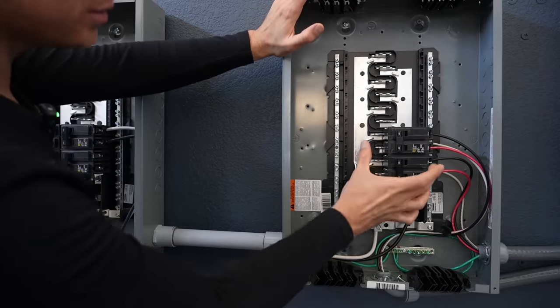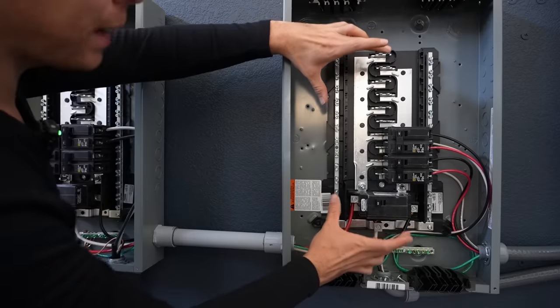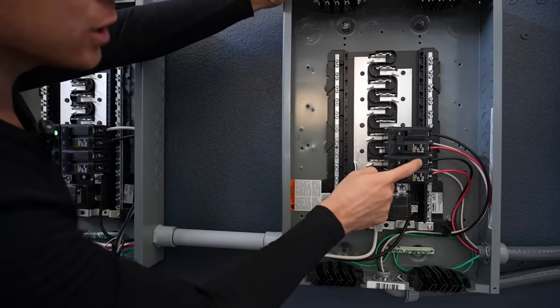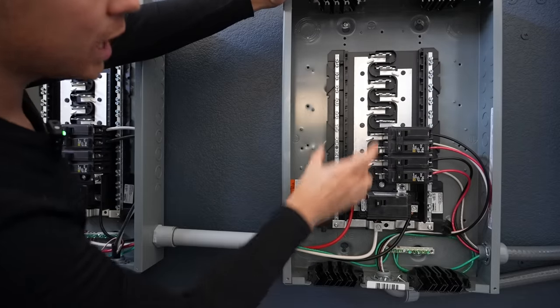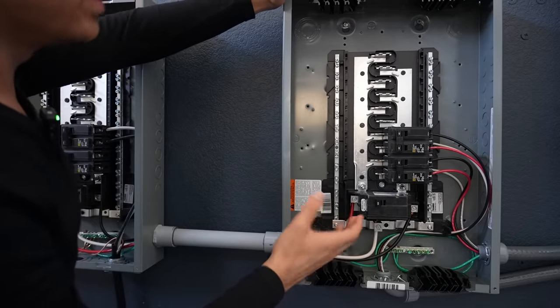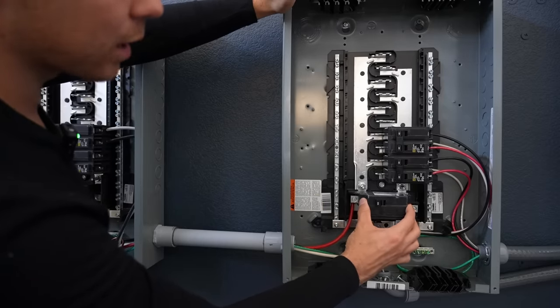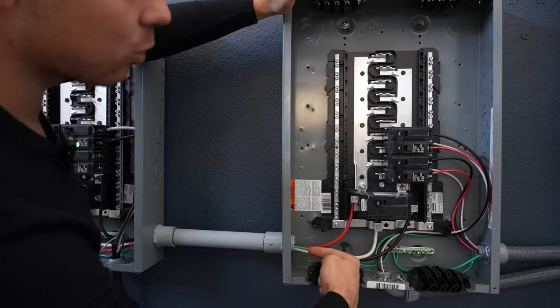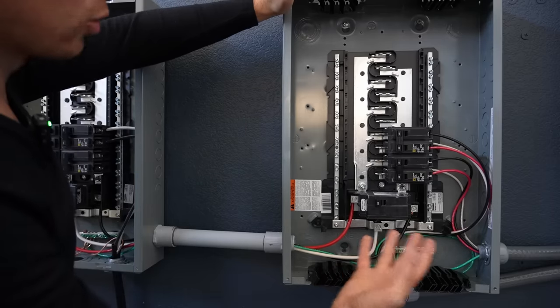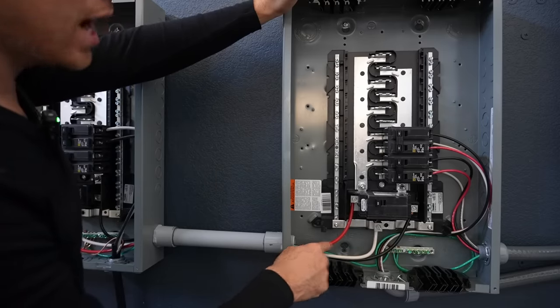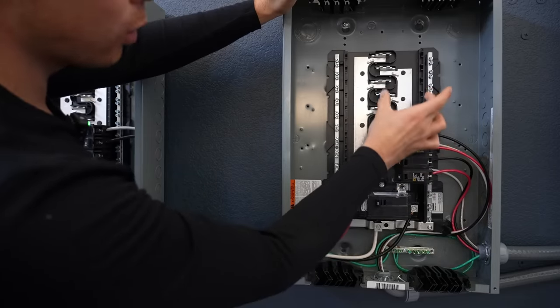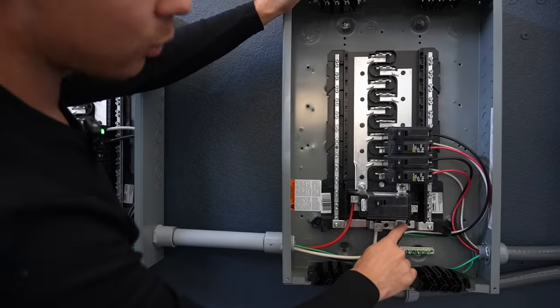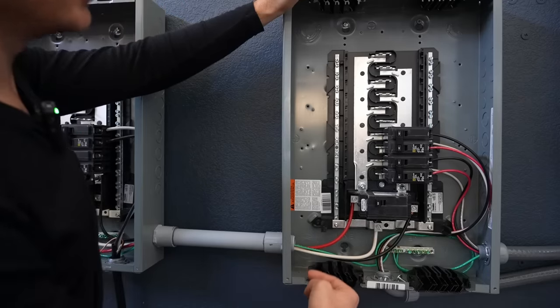These are very easy to install and you can find them at Home Depot or Lowe's. So the whites from the inverter go to the neutral bus bar and then the greens or the grounds go down here to this ground bus bar. Now I'm using this load center for connecting multiple inverters, but that's not the case for everyone. Some of you guys will only have a single panel and you can put all of your inverters on this side and all of your loads on this side. Or if you will not expand your system in the future, you could just have two inverters here and then put load circuit breakers up here and you can easily power your loads. But in this system, because I'm using it as a combiner box, I bought a load center with a main breaker and this switches power for the whole panel. I can take the power from all of the inverters on this bus bar and shoot that out somewhere else to a critical loads panel, to a whole house panel, or whatever I want to power. So I added these conductors down here and these are six gauge.